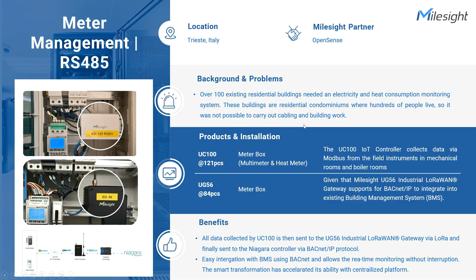So our partner, OpenSense, deployed over 100 units of UC100 controllers and 84 units of UG56 LoRaWAN gateways. The UC100 controllers collected data via Modbus from multimeters and heat meters, and the gateways support data integration into the building management system via supported BACnet/IP protocol. So why replace when you can upgrade? The UC100, UC300 controllers, and EM300DI, all of them are designed for meter upgrades.